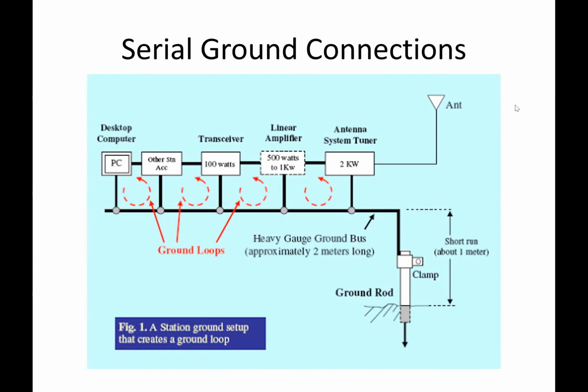Each one has its own connection to this serialized heavy grounding bus. Each one is allowed to develop a voltage between itself, which makes for a lot of noise, and it can make enough noise that you can hear it. The main difference between serial and parallel connections is that a parallel connection has its own ground connected to the same point as all the others.